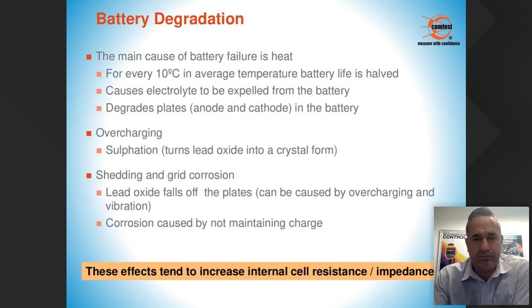Shedding and grid corrosion. Lead oxide falls off the plates and can be caused by overcharging and vibration, shaking the batteries and bumping them, etc. And then corrosion caused by not maintaining charge. The batteries will fail if they discharge. So we need to keep this in mind. So at the bottom, these effects tend to increase the internal cell resistance or impedance. This gives an intro to where we're heading with this.